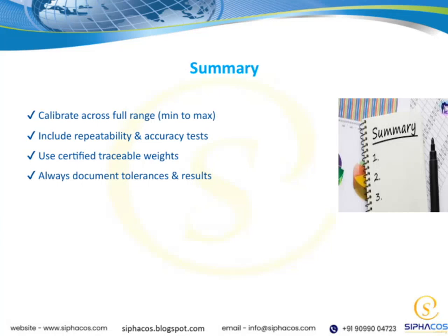Let's wrap up with some key takeaways. First, it's essential to calibrate across the full range, from the minimum to the maximum, to ensure our measurements are accurate throughout the entire spectrum. Next, we should always include repeatability and accuracy tests. These help us verify that our results are consistent and trustworthy. Using certified traceable weights is also crucial, as they provide a reliable standard for calibration and help maintain compliance with industry standards. Finally, never forget to document your tolerances and results thoroughly, because good documentation supports transparency and future reference. Keeping these points in mind will help us maintain precision and integrity in our calibration processes, tying everything together with the overall goal of quality and reliability.